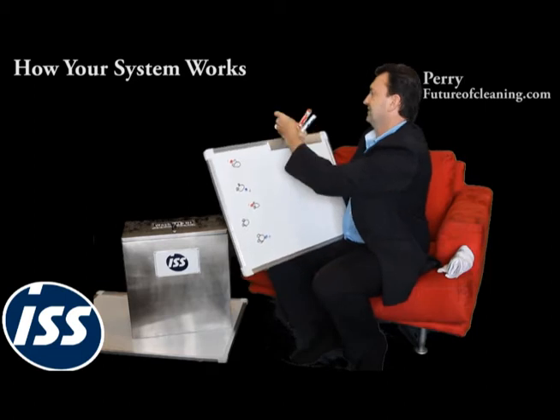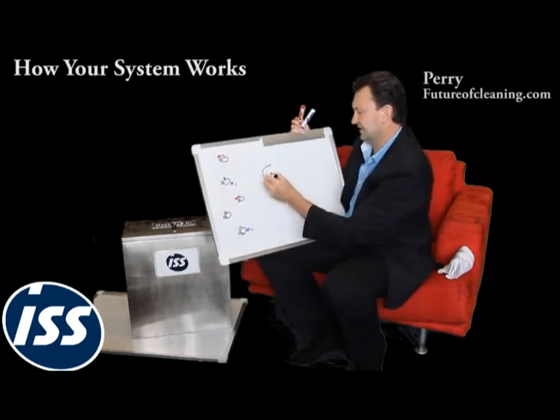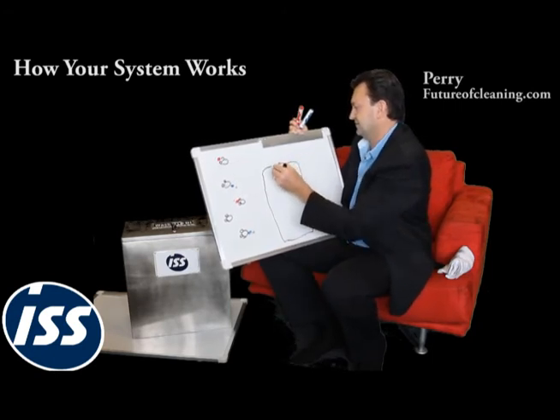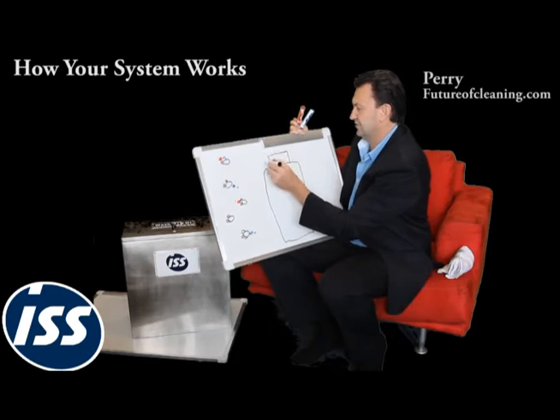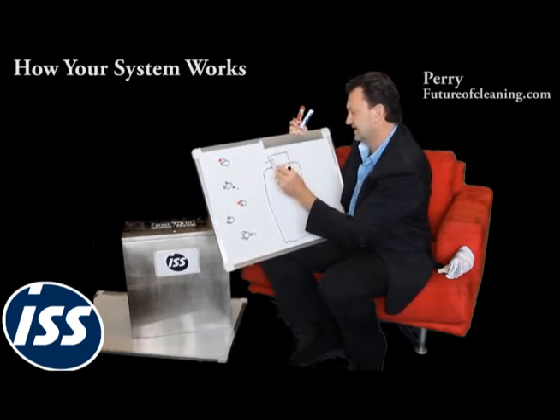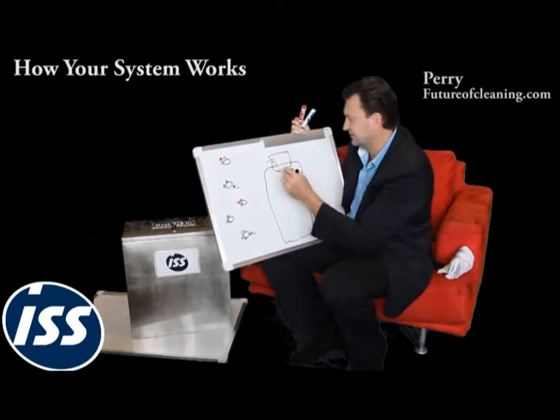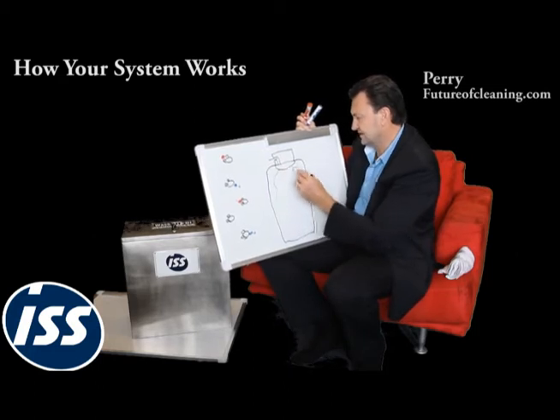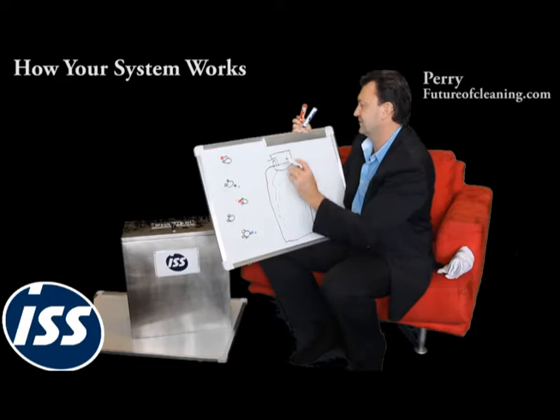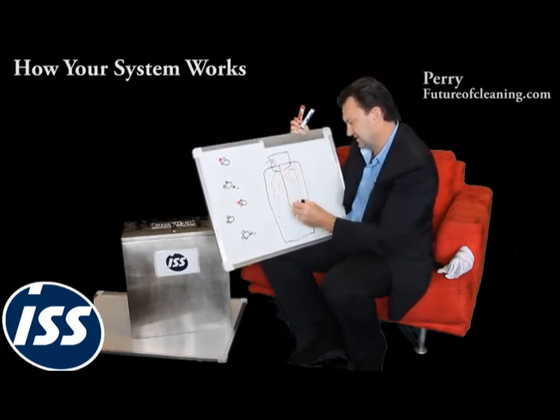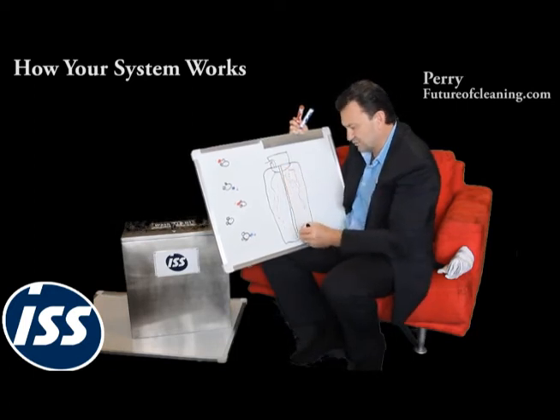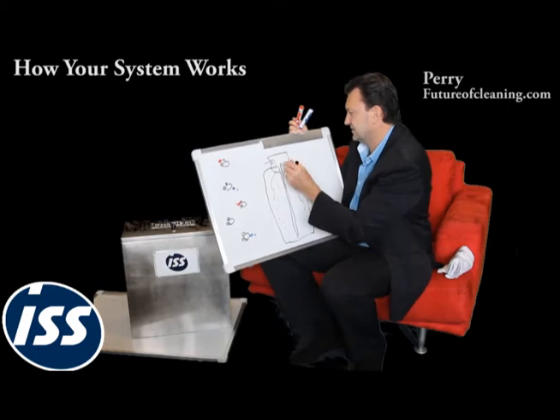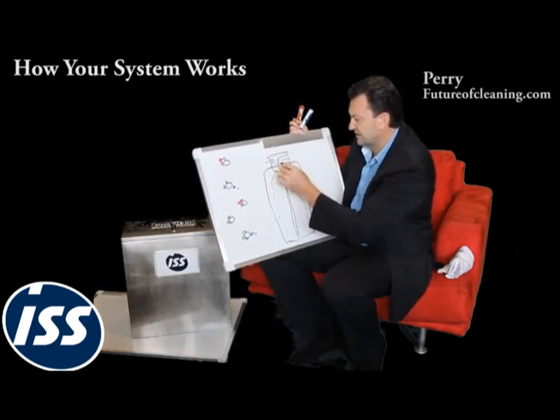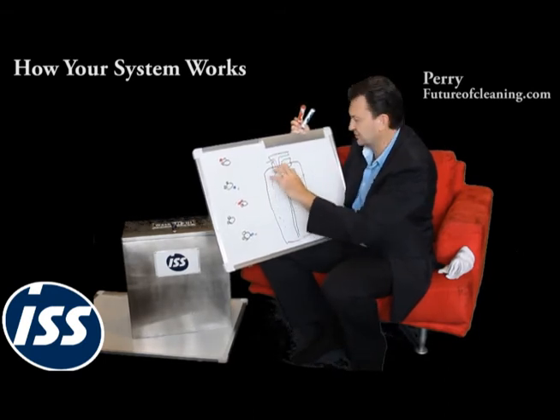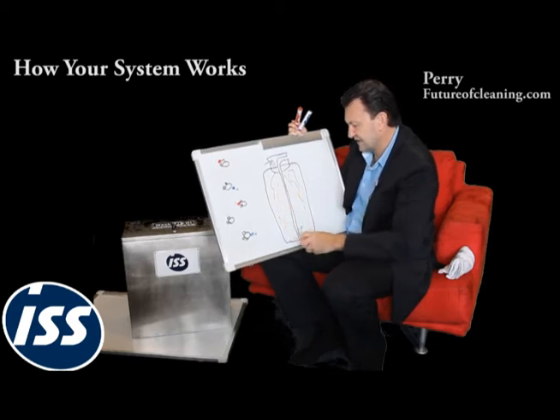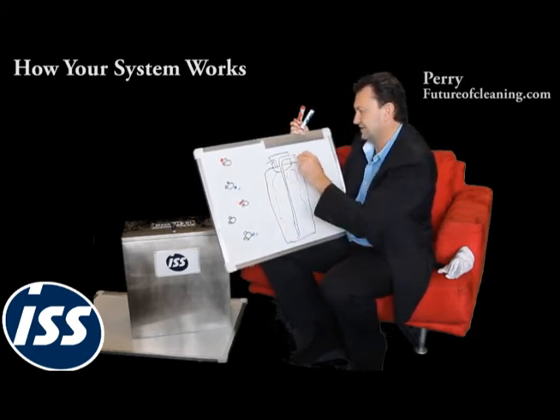And now I'll show you what a DI tank looks like. So the DI tank is the big black tank in your system, and it looks like that. It's got an opening at the top, and when water comes in, it comes into the whole neck of the tank, so the water is distributing itself evenly through the tank from the top. Inside the tank, there's a riser here, and this riser is the way that the water comes out. So the water comes in, evenly distributes itself, works its way through the resin beads, and then it comes to the bottom, and then it comes up and comes out. And that's the way the water flows.